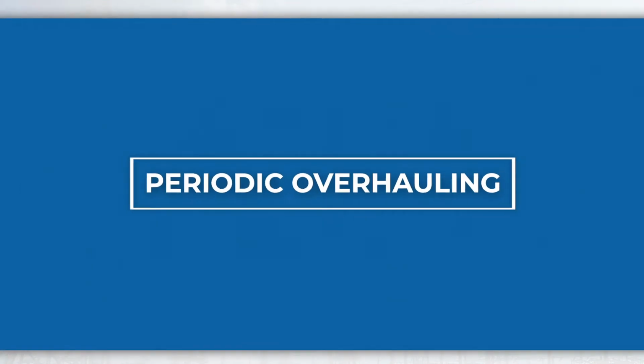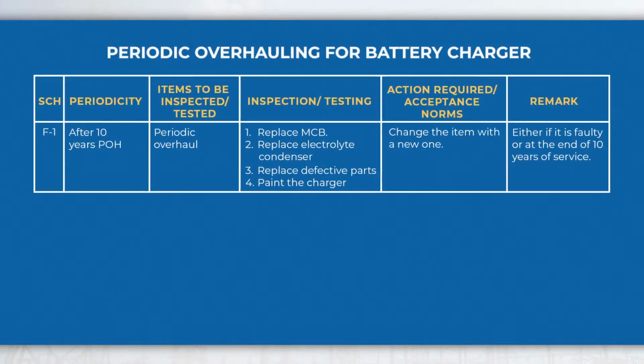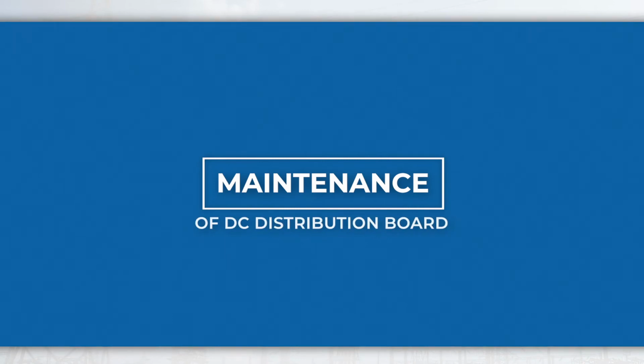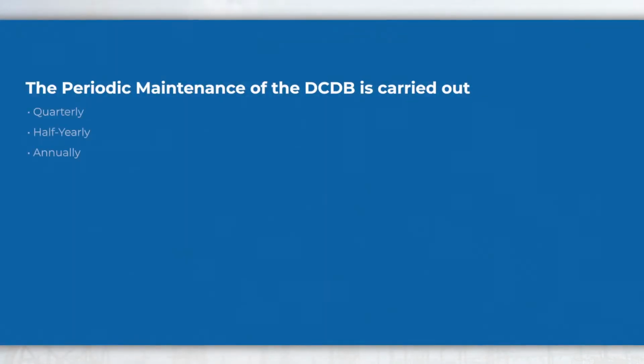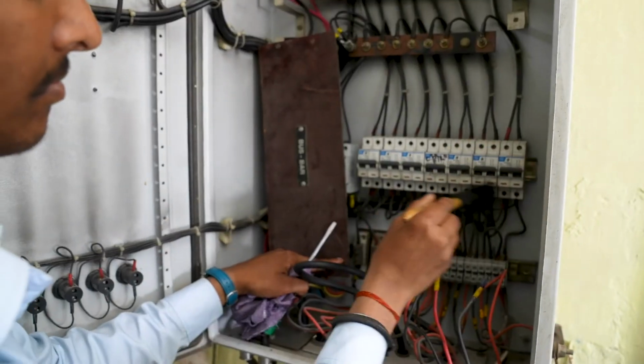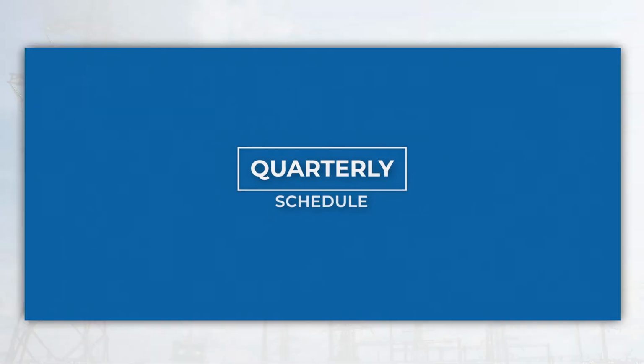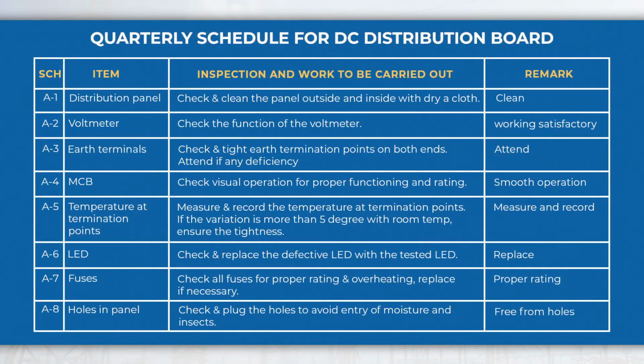Periodic overhauling. Periodic overhauling of battery charger is to be done after 10 years of service, and do the following mentioned in the table. Maintenance of DC Distribution Board. The periodic maintenance of the DCDB is carried out in the following schedules. Maintenance of DCDB. Quarterly schedule: perform activities like checking the function of voltmeter, earth termination points, defective LED and fuses, etc.